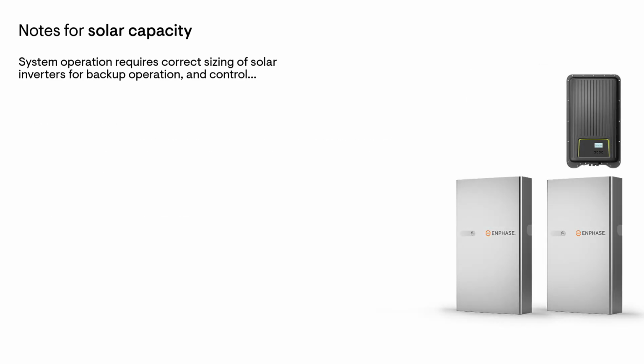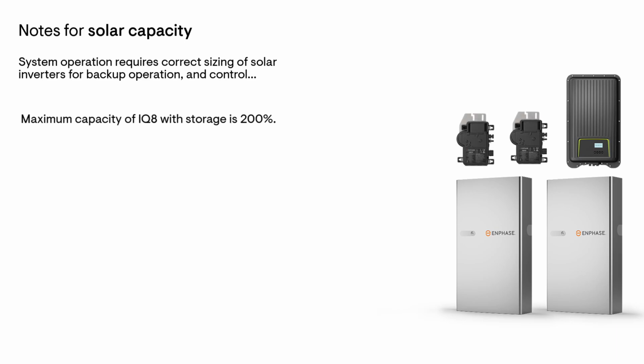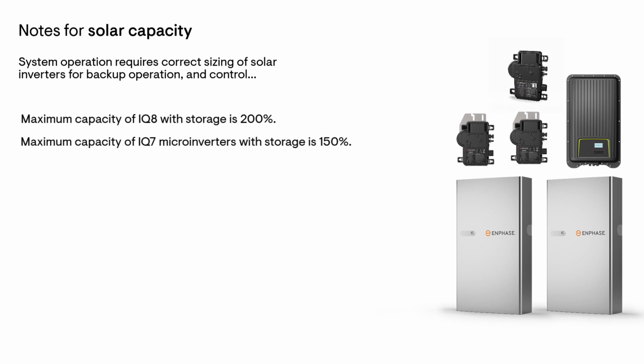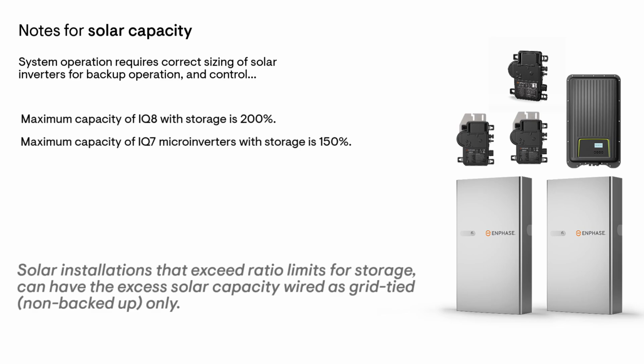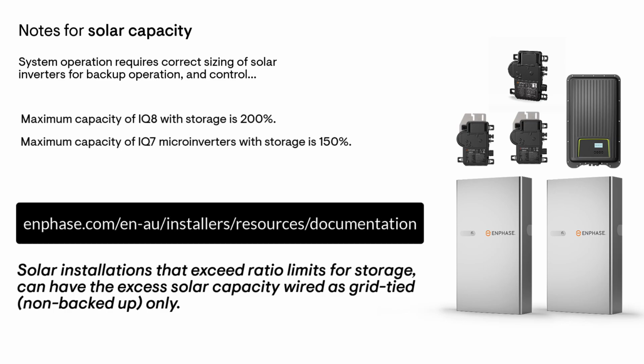Where IQ microinverters are also installed, IQ8 microinverters with storage are limited to 200% oversizing relative to the storage capacity. IQ7 microinverters with storage are limited to 150% oversizing relative to storage capacity. If total PV capacity exceeds these limits, excess PV generation can still be connected as non-backed up solar generation. For further information, refer to the Enphase technical notes and the documentation centre.